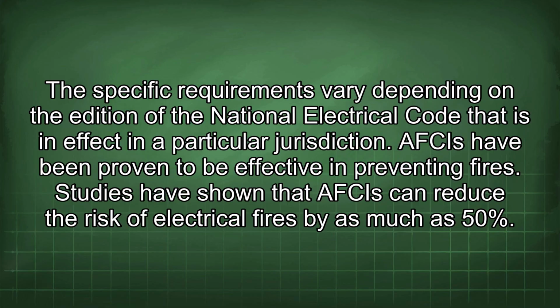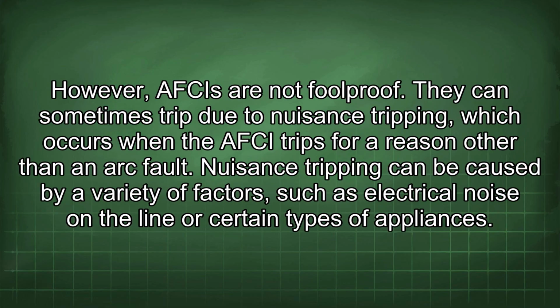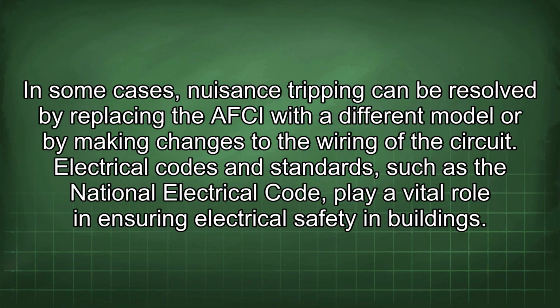AFCIs have been proven to be effective in preventing fires. Studies have shown that AFCIs can reduce the risk of electrical fires by as much as 50%. However, AFCIs are not foolproof. They can sometimes trip due to nuisance tripping, which occurs when the AFCI trips for a reason other than an arc fault. Nuisance tripping can be caused by a variety of factors, such as electrical noise on the line or certain types of appliances. In some cases, nuisance tripping can be resolved by replacing the AFCI with a different model or by making changes to the wiring of the circuit.